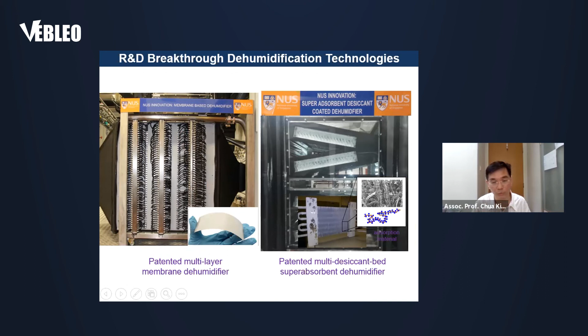The part about removing moisture from the air has already been taken over either by the membrane modules, or by the coated heat exchanger, depending on which one you prefer to use. So what is the impact? Every degree you increase your chill water temperature, your big chiller in your building will enjoy about 4 to 6% increase in COP, or coefficient of performance, and that translates to about 3 to 5% increase in your overall chiller plant energy performance.